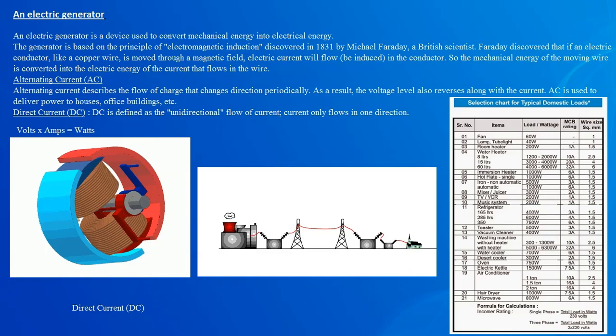14. Washing machine without heater, 1300 watt, 10 ampere, 2.5 square millimeters size wire. Washing machine with heater, 6300 watt, 32 ampere, 6 square millimeters size wire. 15. Water cooler, 700 watt, 6 ampere, 1.5 square millimeters size wire. 16. Desert cooler, 300 watt, 2 ampere, 1.5 square millimeters size wire.